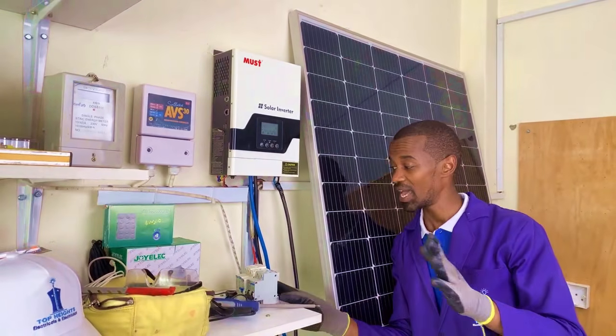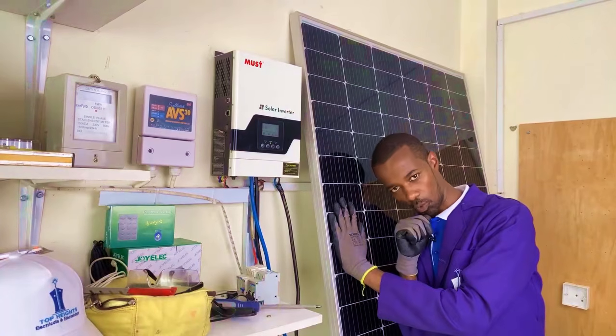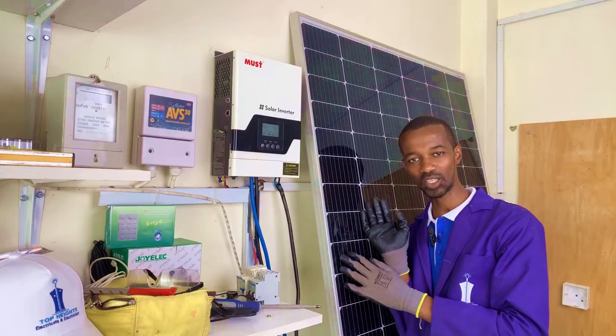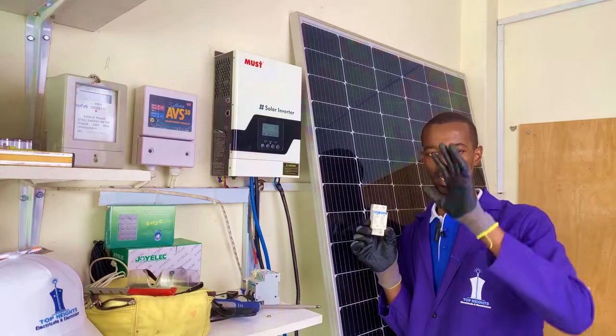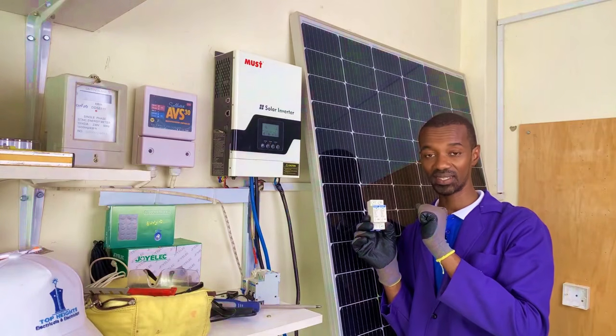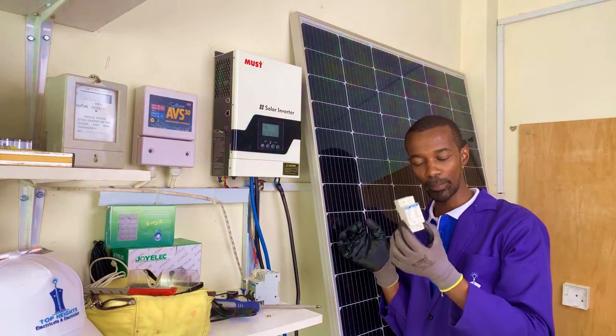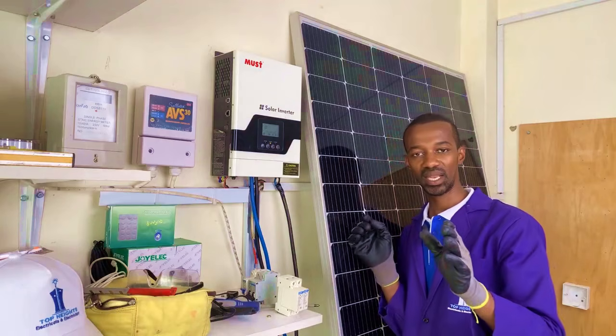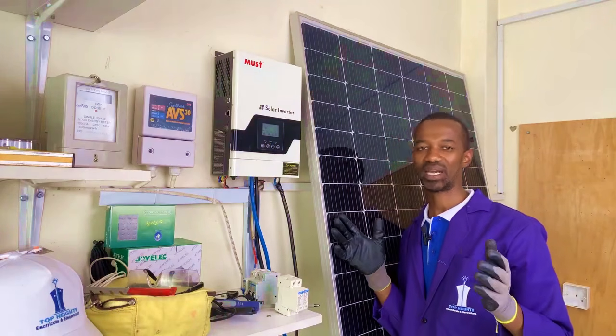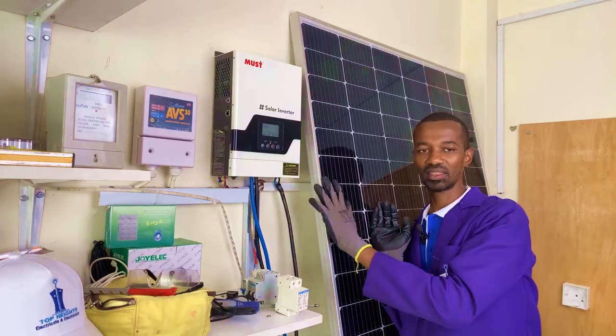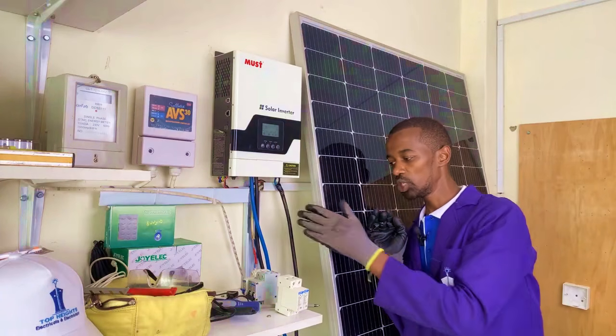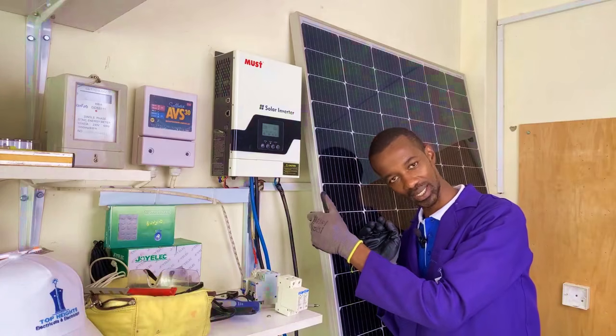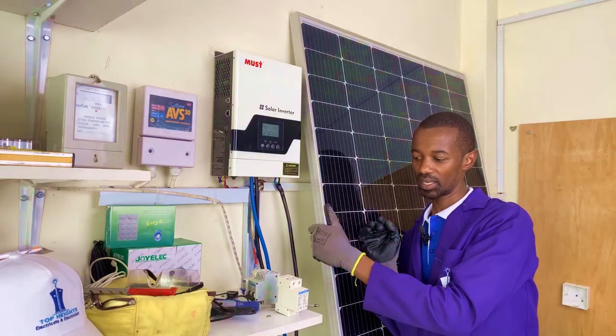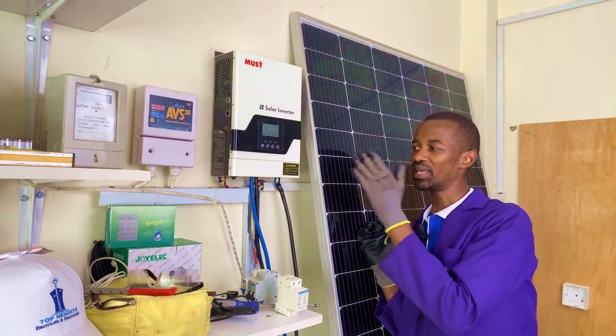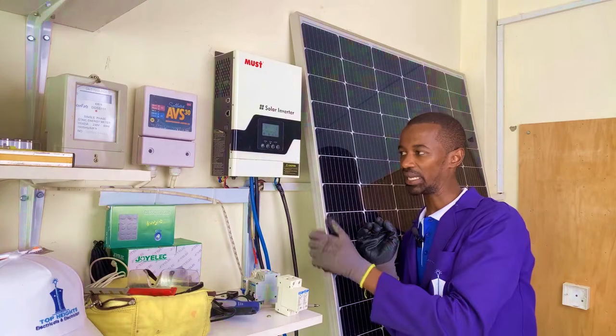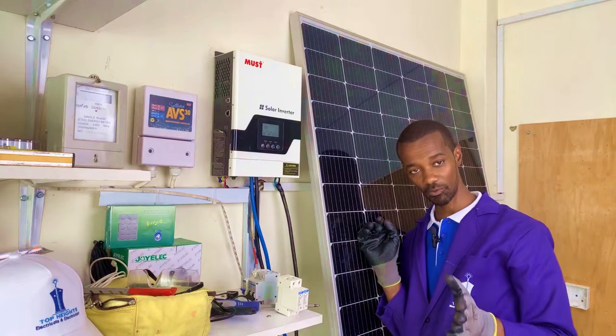There could be surges from the solar panels, for example from lightning strikes on the panels, and these are capped by the SPD on the DC side. There also has to be proper earthing on the solar side. This is where many electricians make a mistake. You must ensure you earth your solar panels. Many people think DC is only about two cables, positive and negative, but you must provide a pathway for earthing. If lightning strikes the panels, it will be redirected to the ground instead of damaging the charge controller or inverter. So you have to create a path for earthing.